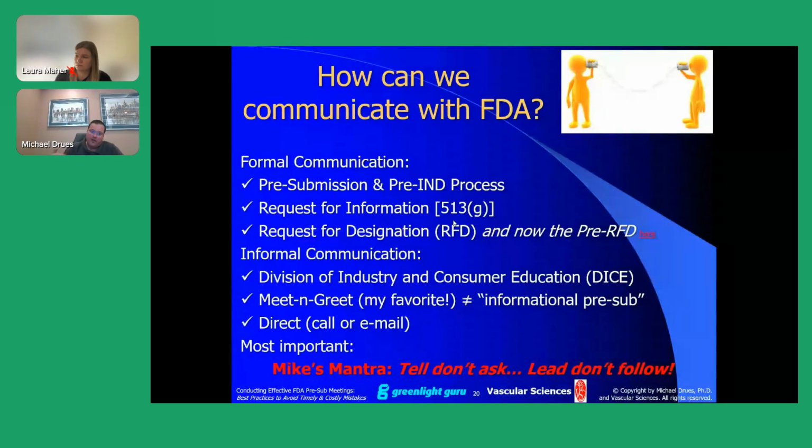Please don't go to the FDA in a pre-sub meeting and ask, is my device a 510K or de novo? What kind of testing do I need to do on it? Do I need to do a clinical trial? That is terrible strategy for a whole bunch of reasons. First of all, it's not FDA's job to tell you what to do. It's your job to figure out what to do and then go to the FDA and sell it to them. And then the second reason why it's terrible strategy, in my opinion, is because you're opening up a Pandora's box and you have no idea what you're going to get.